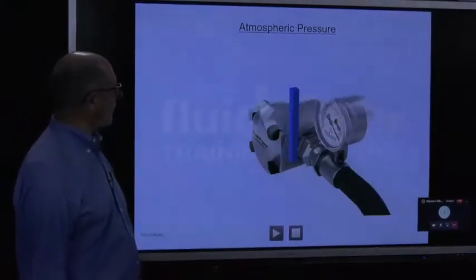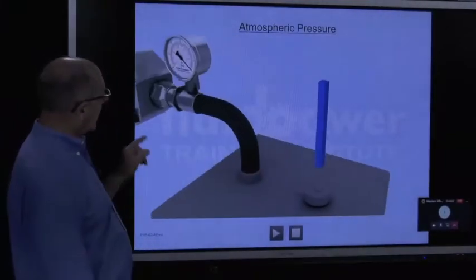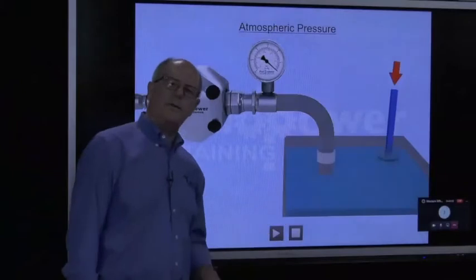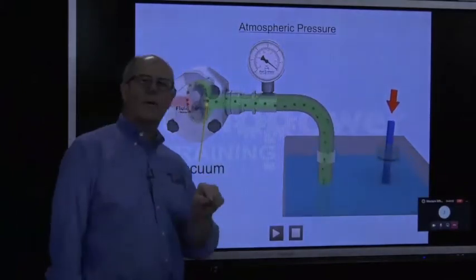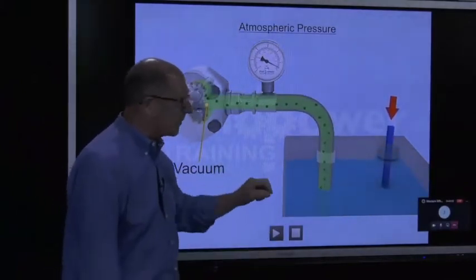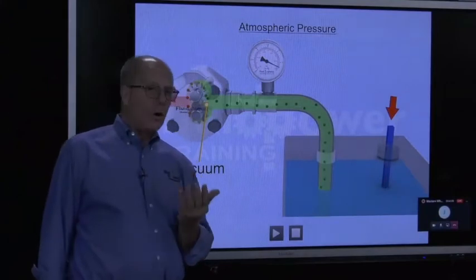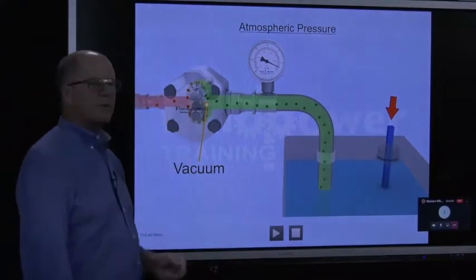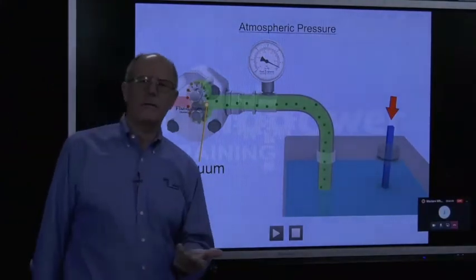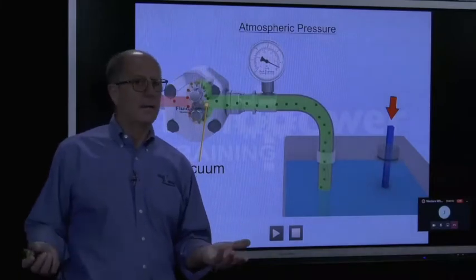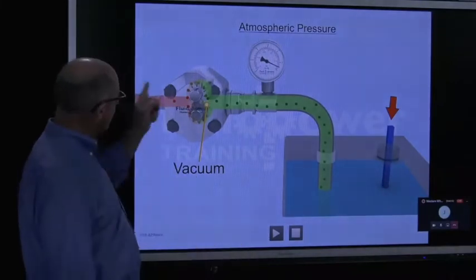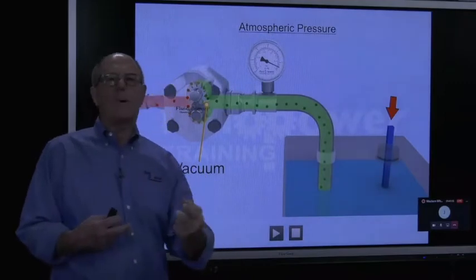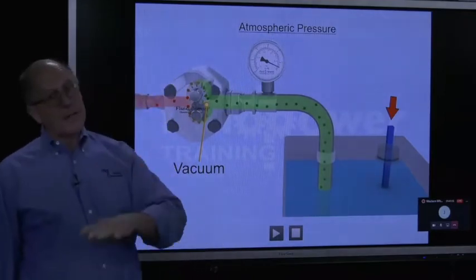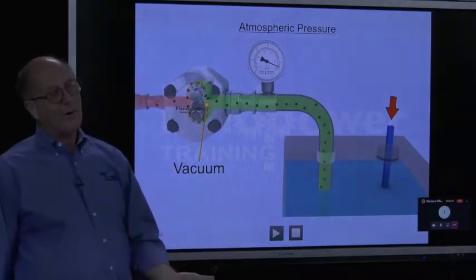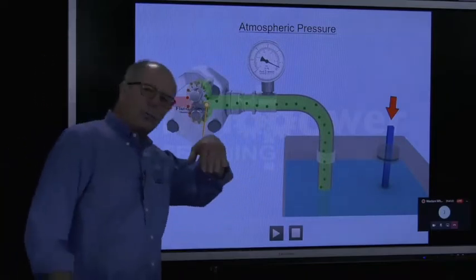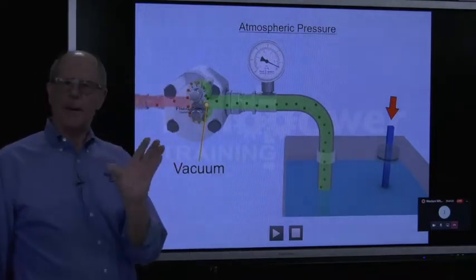Now, take that 14.7 psi through the breather into the reservoir, and you have 14.7 psi pushing down on the oil. All hydraulic pumps are partial vacuum generating devices. So clearly, if I generate a lower pressure in the pump than I have outside the pump, oil is going to flow. It's going to push the oil into the pump.